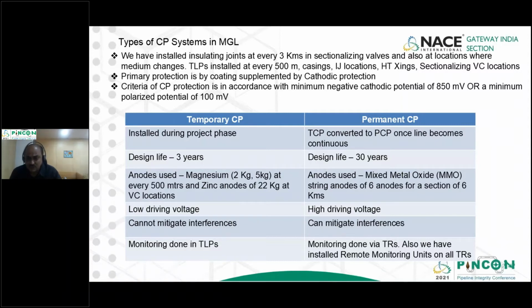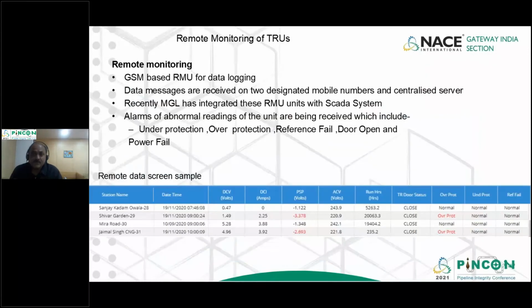Monitoring we do through TLPs, and we have also installed remote monitoring units on all TR units. Now, remote monitoring of TRUs is a GSM-based remote monitoring unit for data logging. Data messages are received on 2 designated mobile numbers, of the people who are in charge of monitoring the network, and they get a message on their mobile number. And then we have now integrated the remote monitoring unit with our SCADA system.